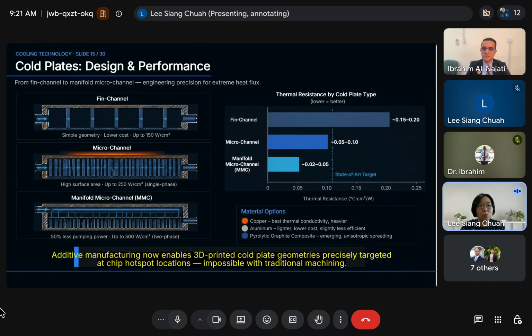Okay, now we look at the cold plate, the key interface between the coolant and the chip. Their design has evolved from simple channels to advanced manifold micro-channel structures. The main goal is to maximize heat removal while minimizing the pressure drop, reducing both the temperature and the pump power. Modern designs can cut the pumping power by up to 50%. And as the design improves, the thermal resistance drops significantly and directly lowers the chip operating temperature.